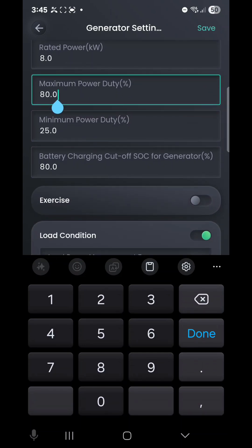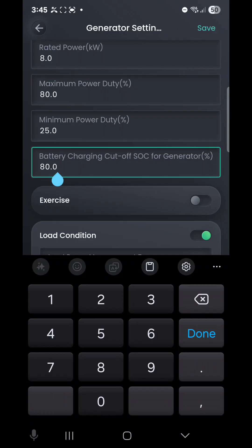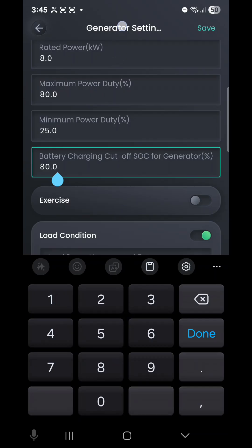Down the bottom here, this is the setting that you can change yourself: battery charging cutoff SOC for generators. The way this is set up currently, the generator will basically turn off once that battery gets up to 80% SOC—SOC stands for state of charge. It won't bring that battery capacity up to 100% and then turn off. That's about minimizing the generator runtime so it doesn't run longer than it has to.